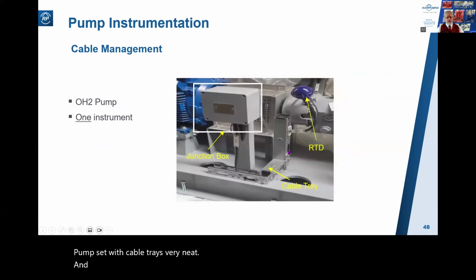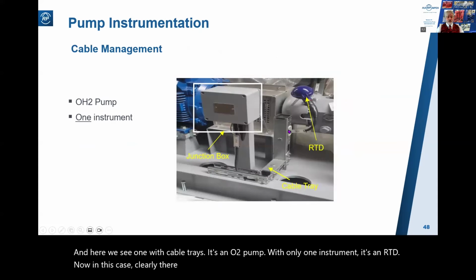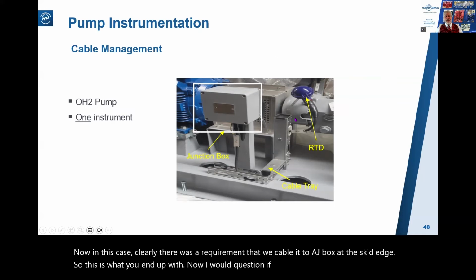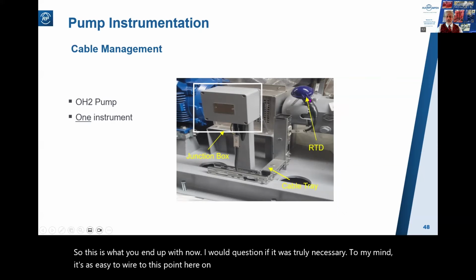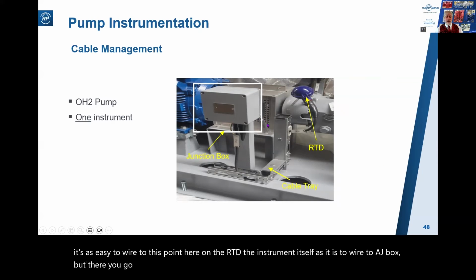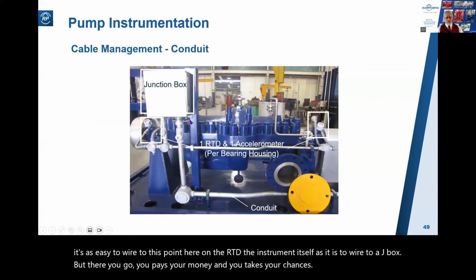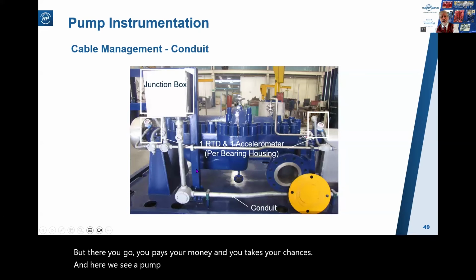And here we see one with cable trays. It's an OH2 pump with only one instrument. It's an RTD. Now, in this case, clearly there was a requirement that we cable it to a J-box at the skid edge. So this is what you end up with. Now, I would question if it was truly necessary. To my mind, it's as easy to wire to this point here and on the RTD, the instrument itself, as it is to wire to a J-box. But there you go. You pays your money and you takes your chances. And here we see a pump that is run with wiring in conduit.